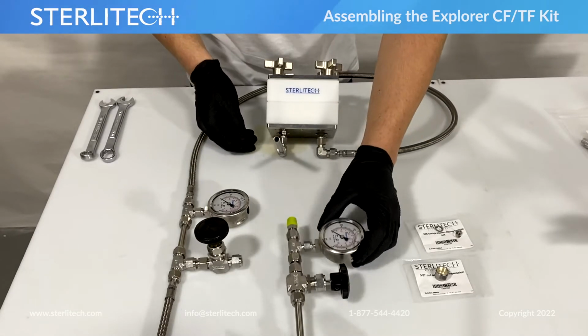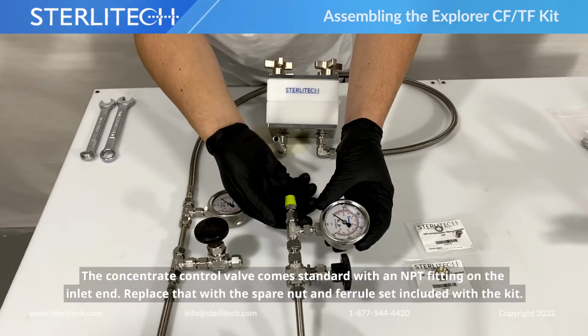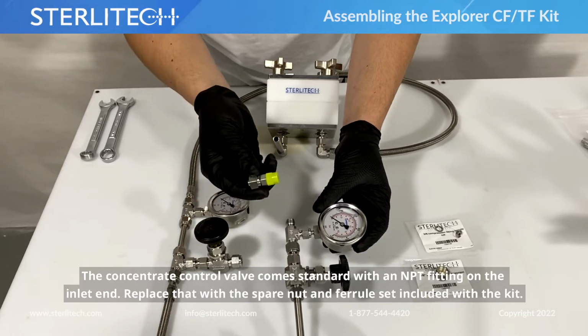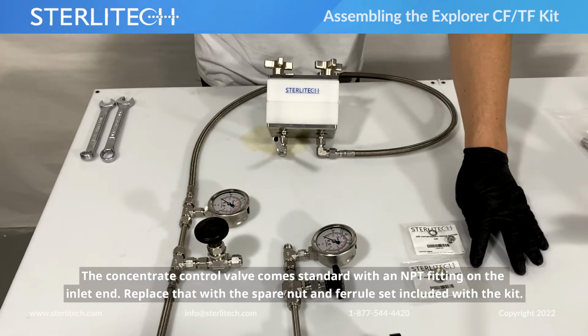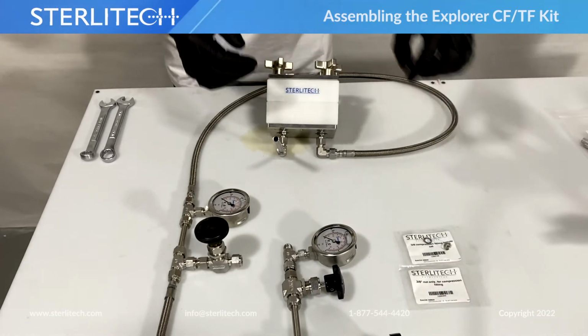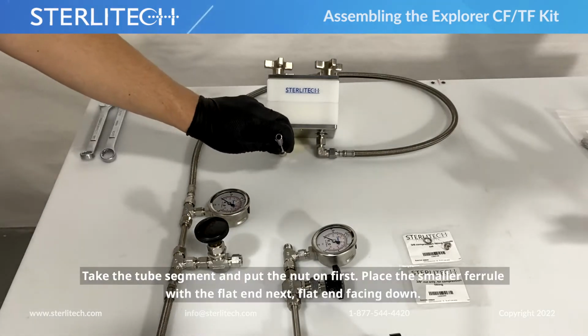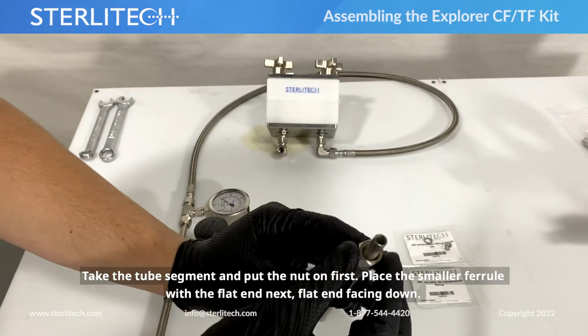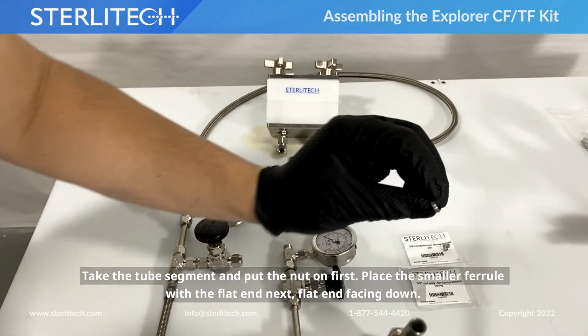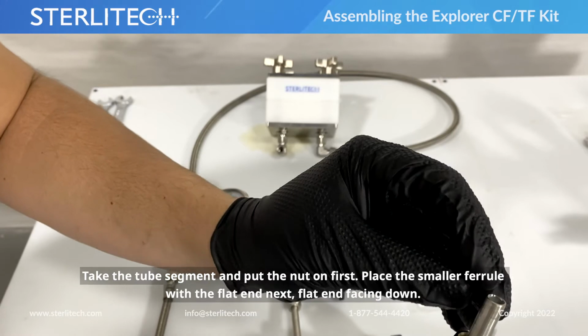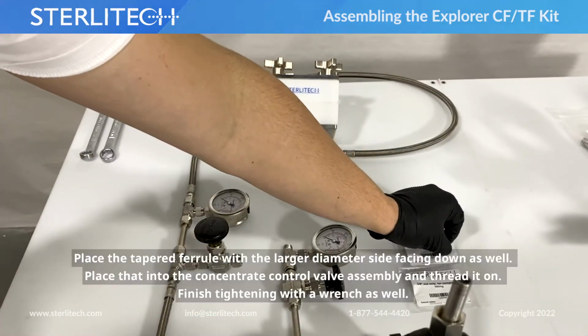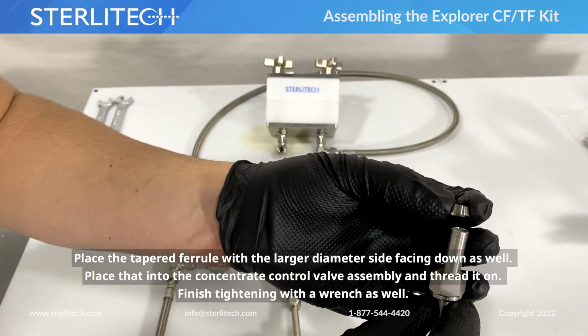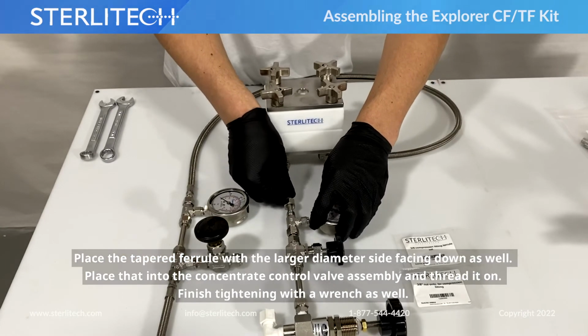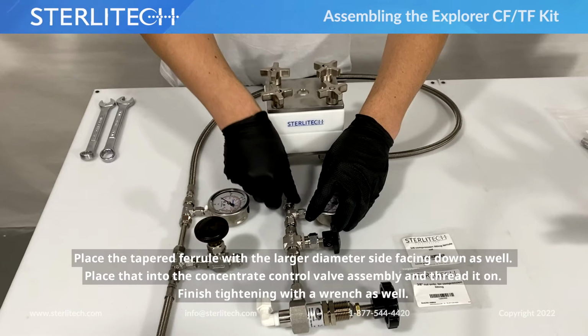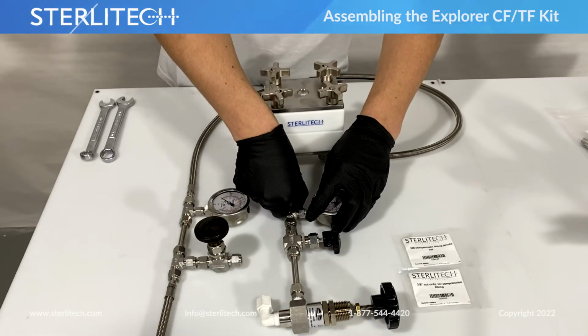Moving on to our concentrate control valve. It comes standard with an MPT fitting on the end, on the inlet. We're going to need to replace that with the spare nut and ferrule set that comes in your kit. Best way to make sure we get this correct is I like to take the tube segment. I'll be putting my nut on first, and then we'll be placing the smaller ferrule with the flat end on next, flat end facing down, and then we'll take our tapered ferrule with the larger diameter side facing down as well, just like that. From there we can place that onto our concentrate control valve assembly and thread that on. Make sure you finish it off with the wrench as well.